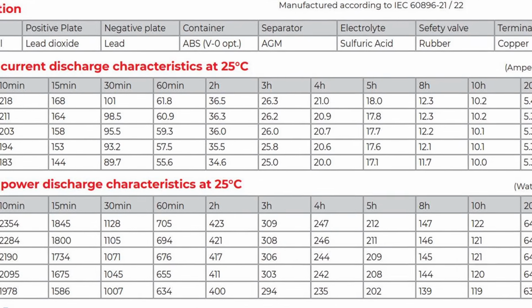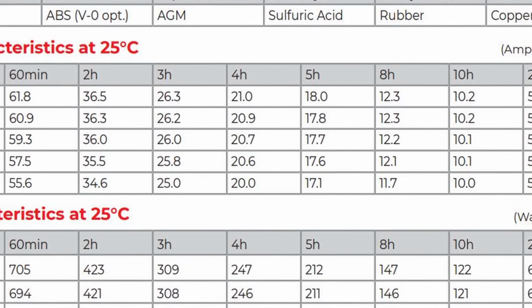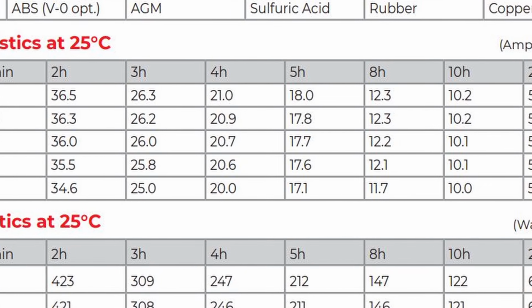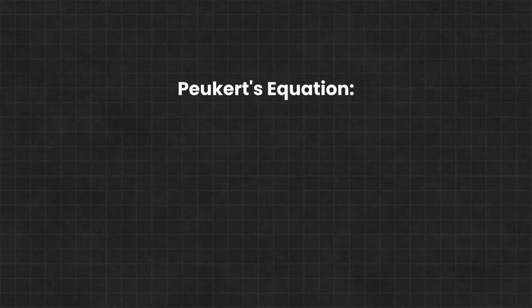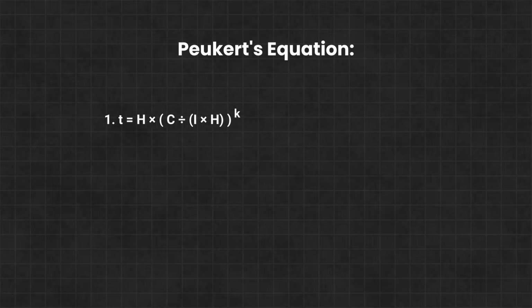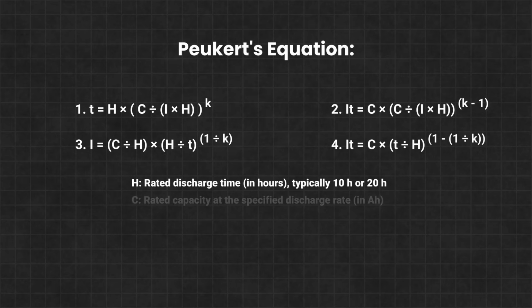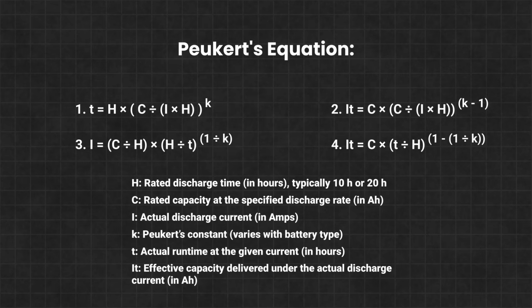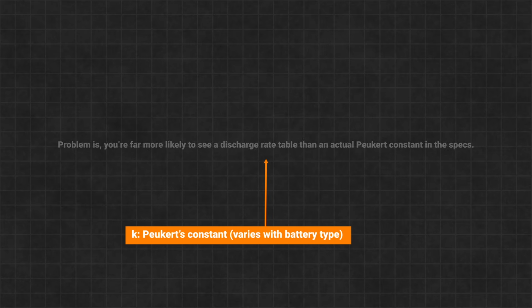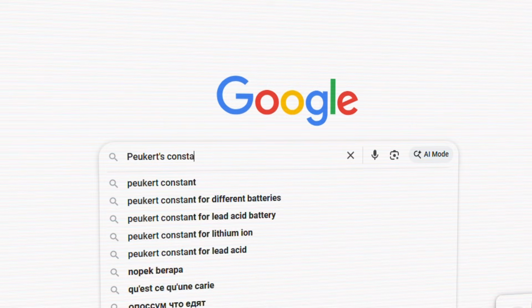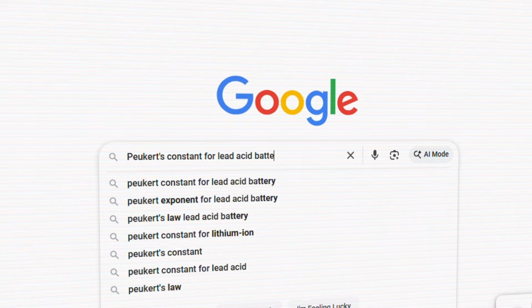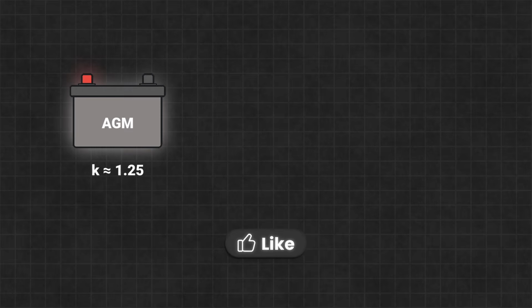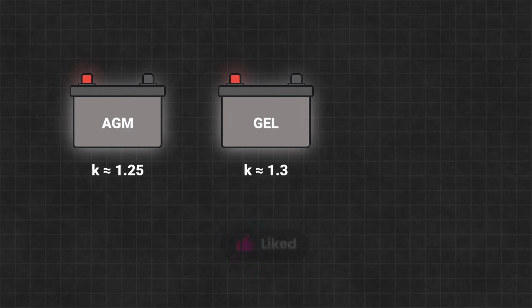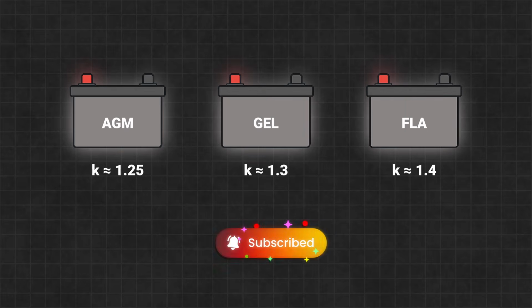Now, if you don't have access to a table that estimates the effective capacity of your battery at different discharge rates, you can actually estimate it using Peukert's equation. Here's the basic formula, and it can also be written in a few different ways. So all you need is the Peukert constant, which depends on the battery you're using. The problem is manufacturers don't typically provide the specific Peukert constant for their batteries. So I did some digging and some calculations, and here's a good rule of thumb. Use 1.25 for AGM batteries, 1.3 for gel batteries, and 1.4 for flooded lead acid batteries.